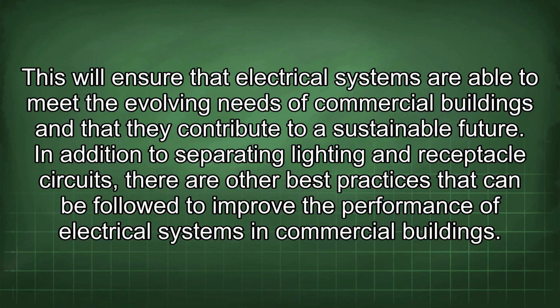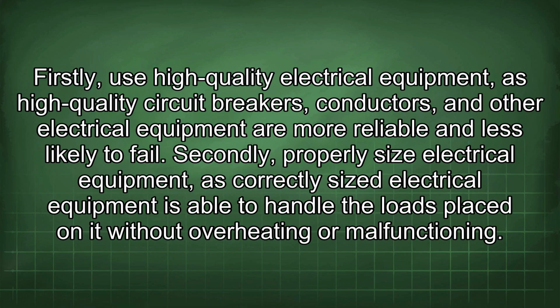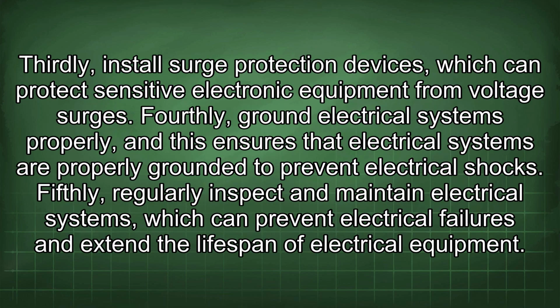In addition to separating lighting and receptacle circuits, there are other best practices that can be followed to improve the performance of electrical systems in commercial buildings. Firstly, use high-quality electrical equipment, as high-quality circuit breakers, conductors, and other electrical equipment are more reliable and less likely to fail. Secondly, properly size electrical equipment, as correctly sized electrical equipment is able to handle the loads placed on it without overheating or malfunctioning. Thirdly, install surge protection devices, which can protect sensitive electronic equipment from voltage surges.